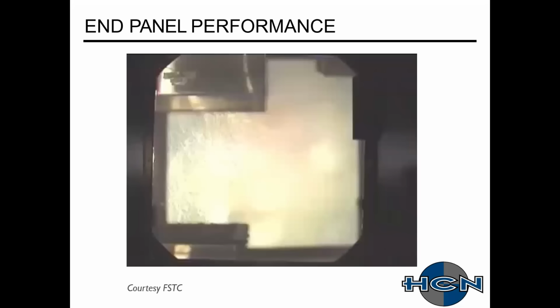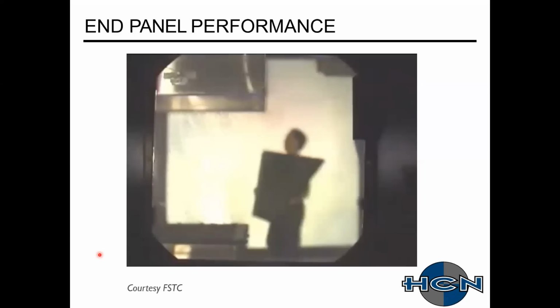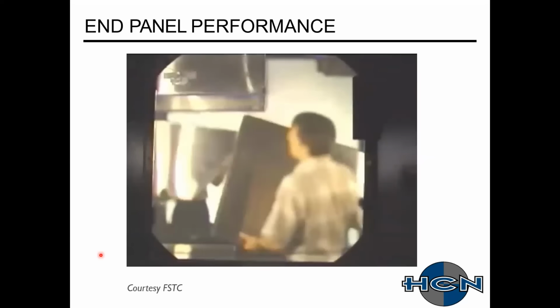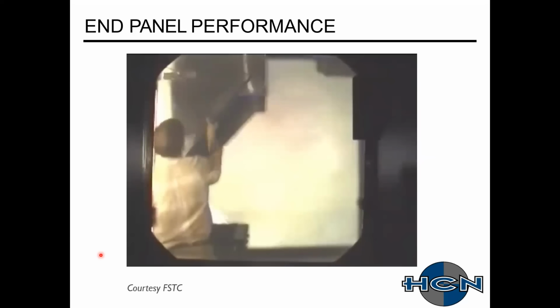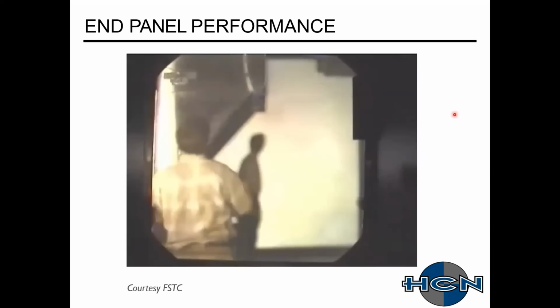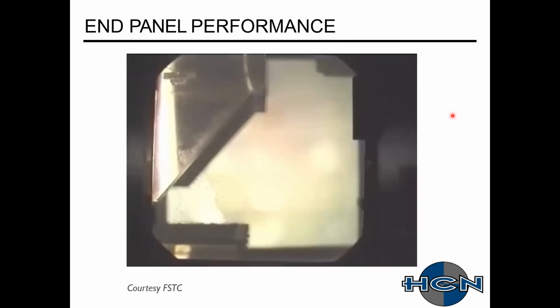Here is a video I'm going to show you where this hood is not capturing appropriately, and you'll see the smoke rolling out. And then they come and place in panels. Let's see if it's still rolling out. Just by placing some panels, we've taken a hood that was failing and made it a robust design that's capturing that radiant load that was lost to the space, which would have been put on the HVAC returns, adding extra load and making your line cooks very uncomfortable, hot, and complaining.